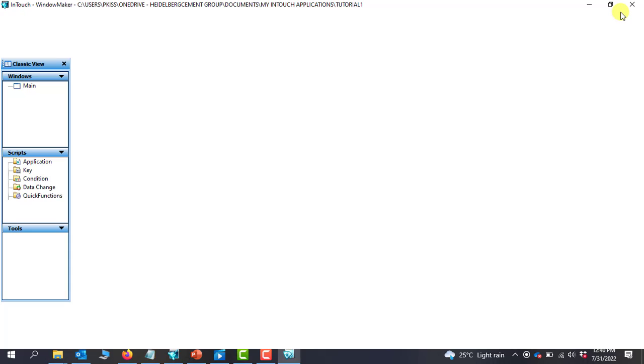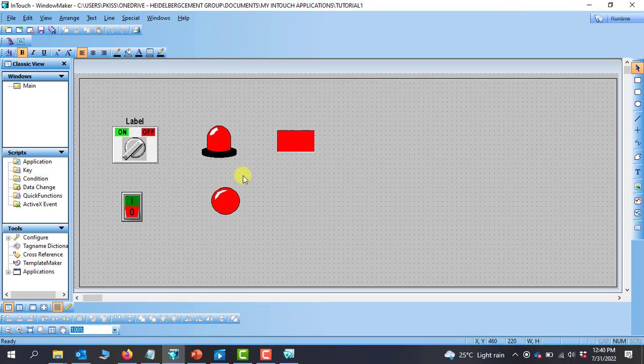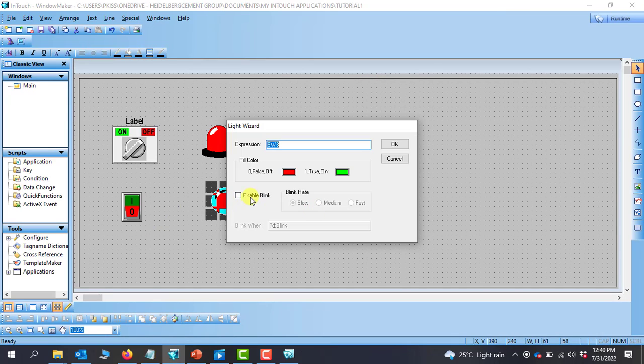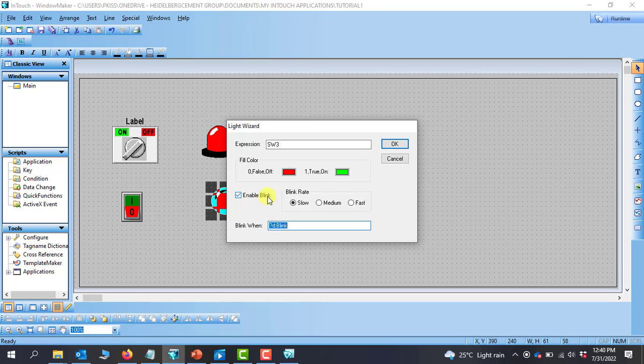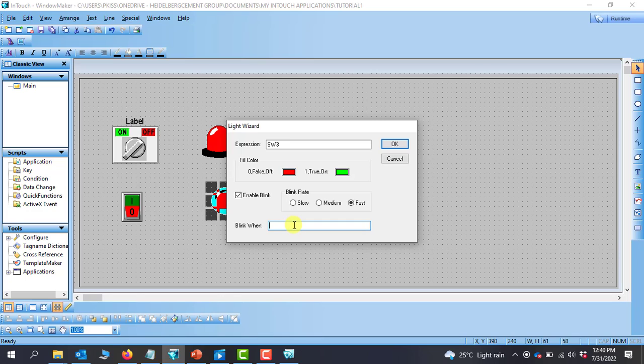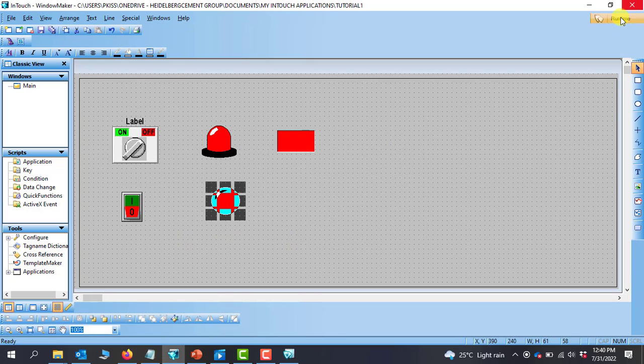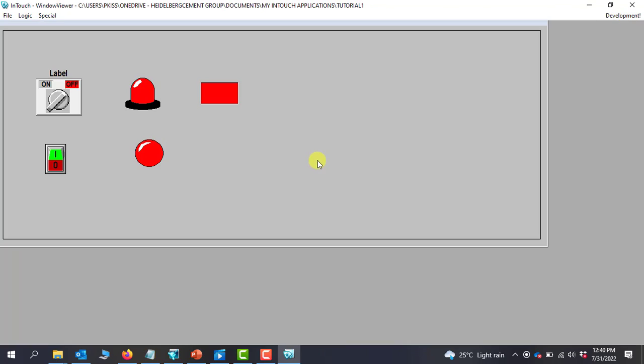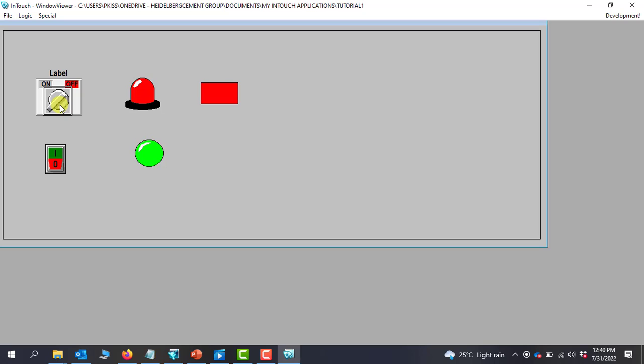Okay, switch it back off. And then I go back to the development page. I double-click on this one and also cause it to blink. So I enable blink and then we can see we have slow blink, we have medium, and then fast. This time I want this one to flash faster, and then I have to put the condition. The condition is that when switch three is on, then it can start flashing. Okay, I'll go back to runtime. And then when I turn switch three on, we can see how it's flashing. And when I turn this switch on, you can see the rate of flashes.